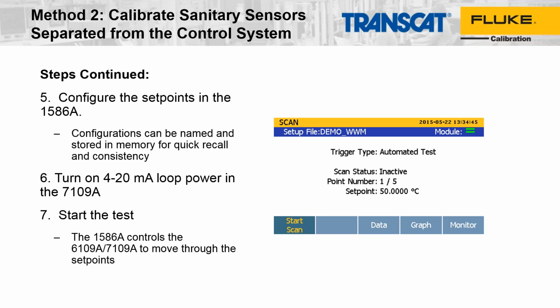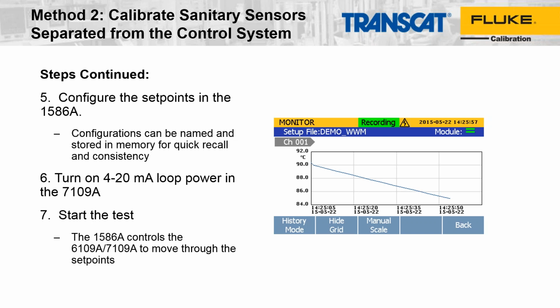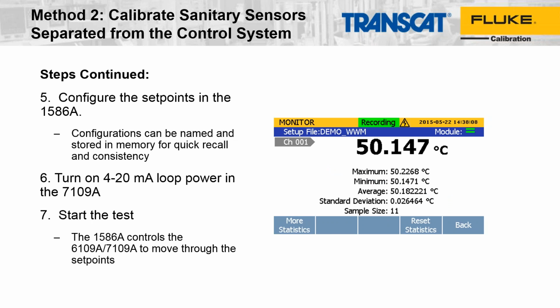So we're also simultaneously going to be calibrating the 4 to 20 milliamp loop on the transmitter by using the 7109A. So we have to go into the 7109A and enable loop power to energize that circuit so that we can calibrate the transmitter. So we start the test, and then we start going through the different set points. Similarly, the 1586A will have a graph mode if you want to see the graph of the temperature as it's going.